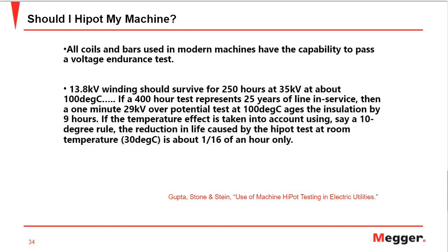So they've taken an example of a motor. If it runs for 400 hours and represents 25 years of service, then 1 minute of a 29 kilovolt overpotential test at 100 degrees Celsius would take down the insulation by 9 hours. While if we do a DC hypot test at 30 degrees Celsius, it can only do about 1/16th of an hour, which is about 3 or 4 minutes, compared to the 9 hours which the motor experiences every time in regular operations.